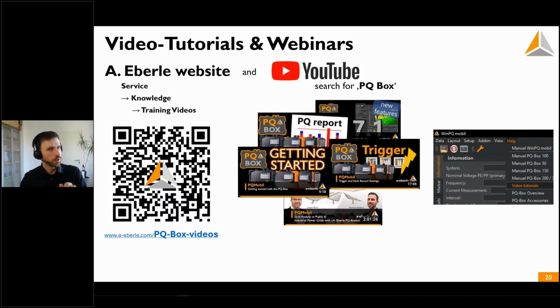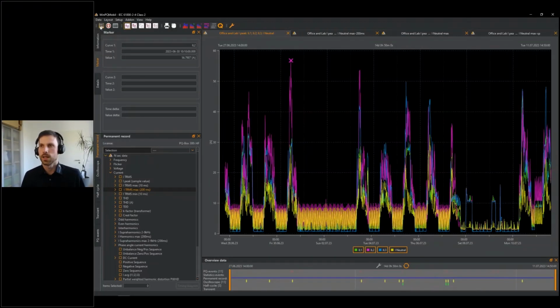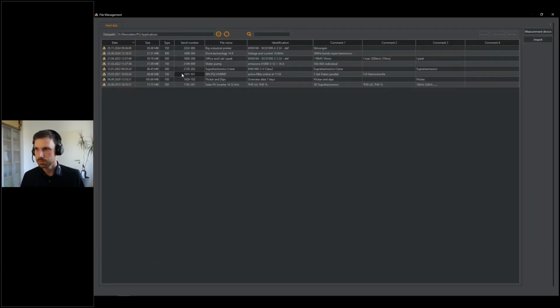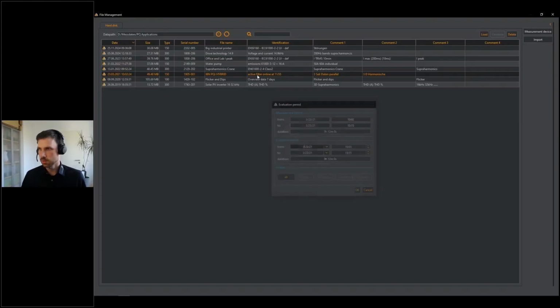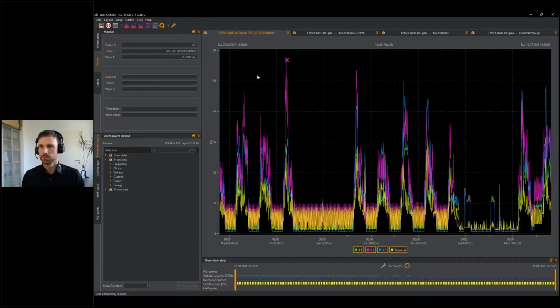And so, okay, what was this? You open the door and see, oh no, the voltage probe, for example, of phase 1, 2, or 3 dropped because it was not connected that well. So, well, is my measurement file useless now? No, it is not. And I will show you why. I'm going to open the next measurement. And so this is, for example, something. In this case, the voltage probe did not drop, but the thing I'm going to show you, the tools are also good for this use.